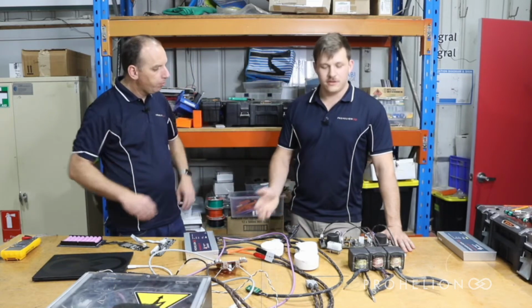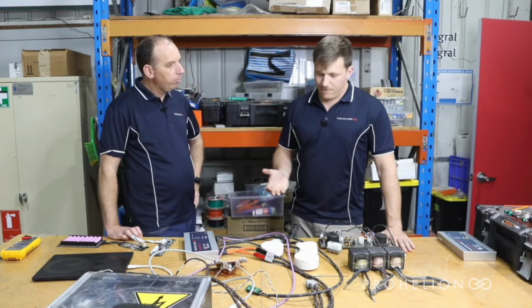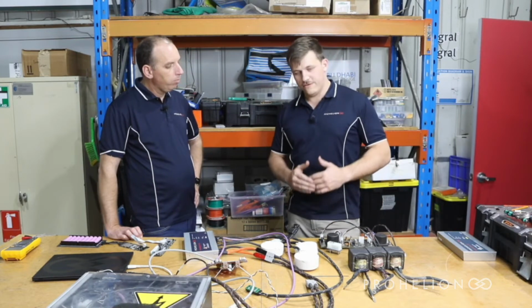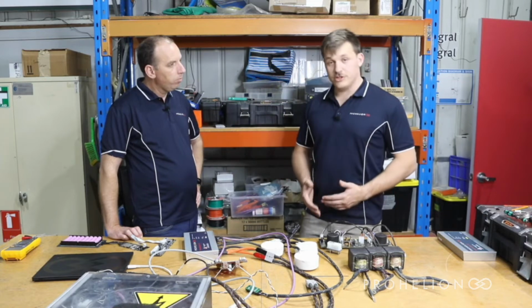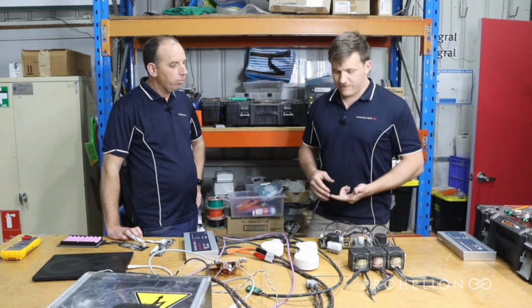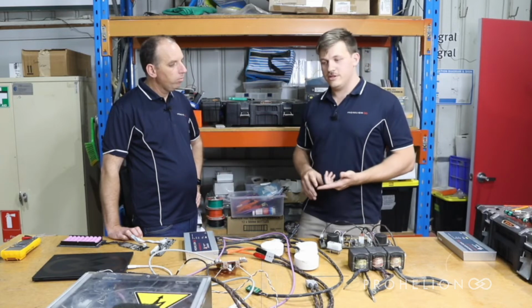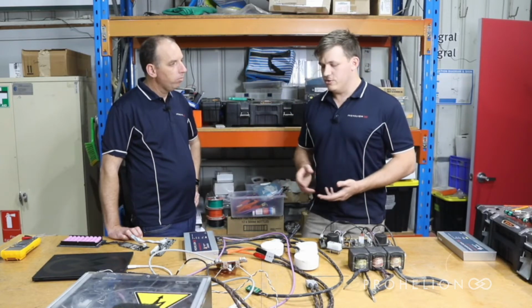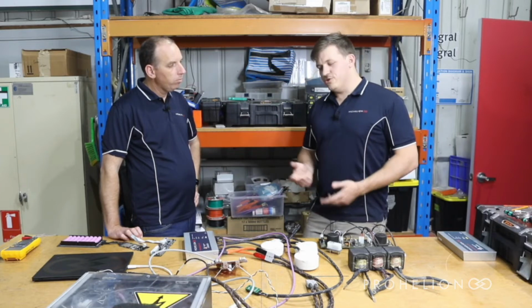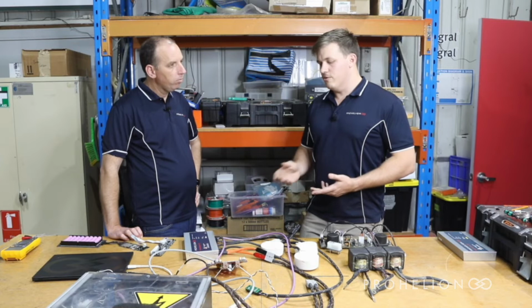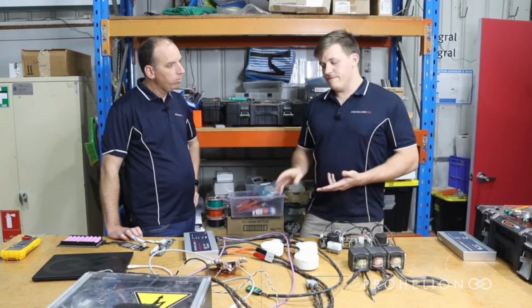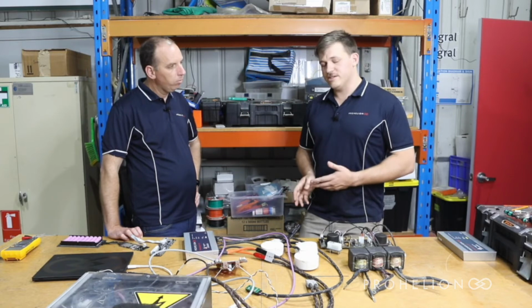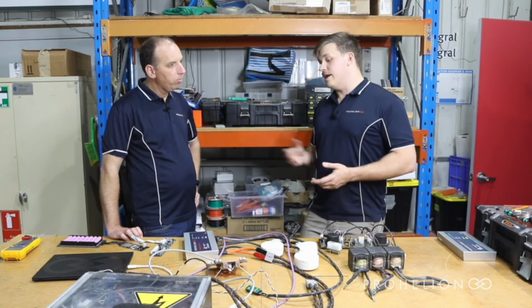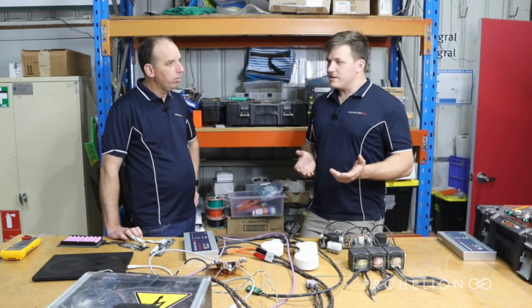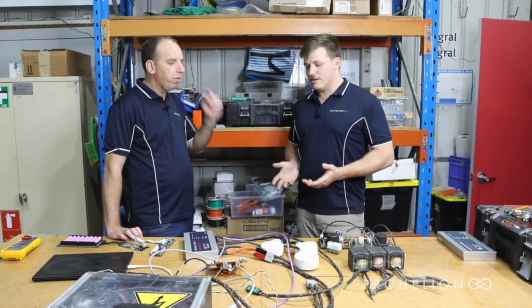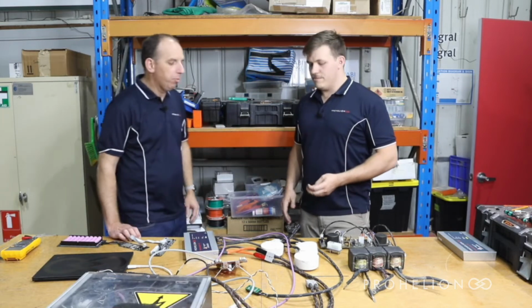Exactly right. So in the Prohelion manual for our BMS, there's a whole chapter on selecting the correct size precharge resistor for your system, and it takes into account your system voltage, so your battery voltage, and your bus capacitance. Your bus capacitance usually is indicated on your motor controller datasheet. If the OEM of the motor controller doesn't specify the bus capacitance, sometimes that can indicate that it handles its own precharge. But I wouldn't make that assumption, because you can get a bit unstuck there. Risky assumption to make, right? If you get it wrong, you're potentially going to end up with damage.